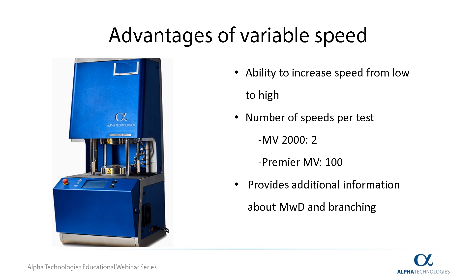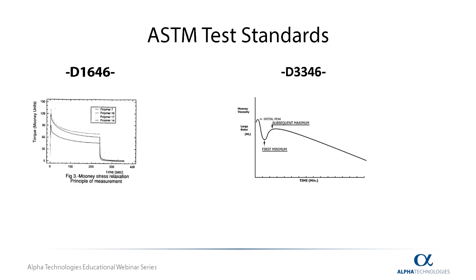This dynamic test will provide extra information about the shear thickening and thinning of a material as well as molecular weight distribution and polymer chain branching. The Premier Series Mooney viscometer adheres to two main American Society for Testing and Materials standards: ASTM D1646 and D3346.